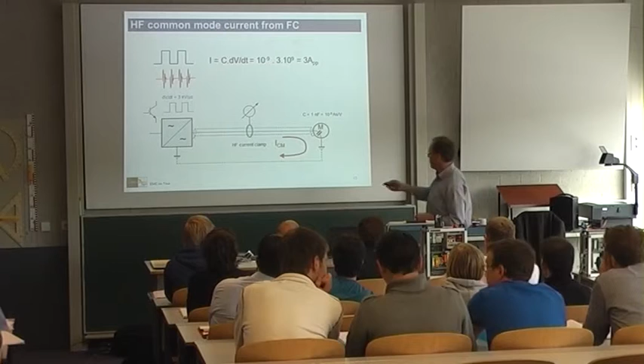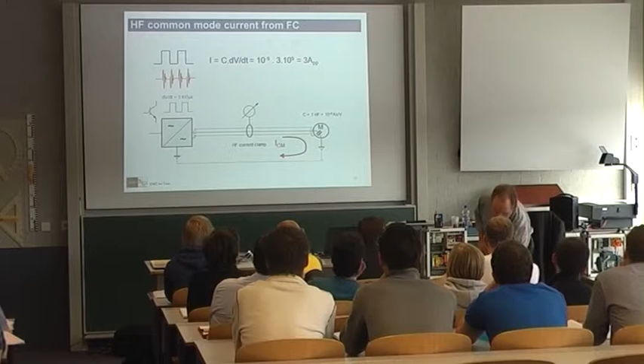So this is the circuit what I've got here. I've got my variable speed drive, the box here. I've got my electrical motor, which is on the field side. And I've got a screened cable. So there's some braiding actually around the cable. It actually has 3 conductors, so 3 phases going to the winding and then capacitance to the earth. So this makes the common mode loop. And we can make an estimate by using this capacitance, 1 nanofarad, we can actually measure on motor terminals. And then with the dV/dt, we get some number of amps, peak value, of current going this way, back to the source, always back to the source.